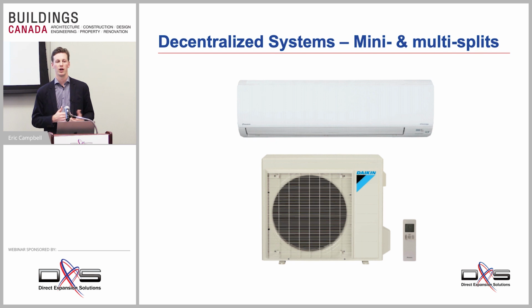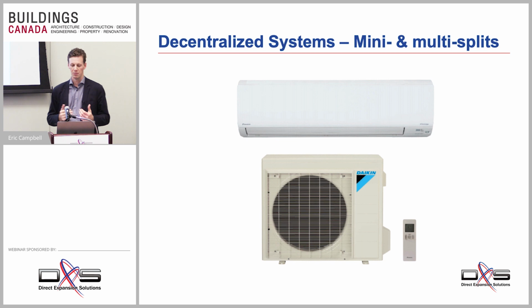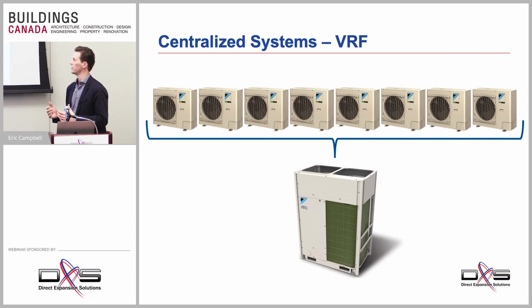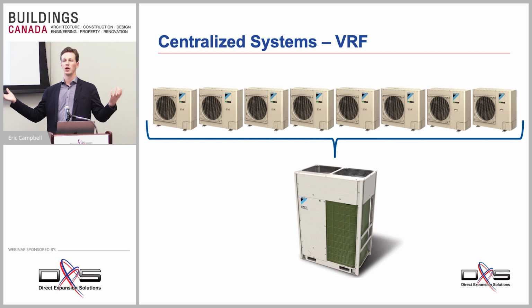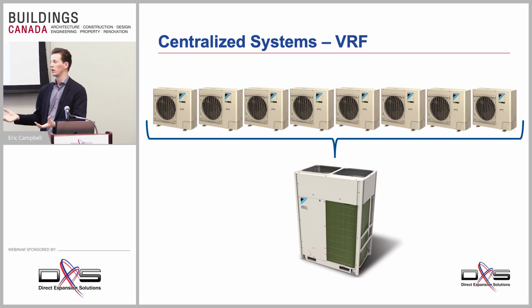These are typically one-to-one, where you've got one indoor unit and one outdoor unit. It doesn't necessarily have to be a wall-mounted ductless unit like we've shown here. There are ducted options and things like that. But simply, it is mostly a one-to-one or a two-to-one or three-to-one, where you've got maybe up to 3 indoor units connected to one outdoor unit. We'll talk later on, when we get into the design applications and considerations, about when we use this decentralized solution versus the centralized VRF solution. So VRF is like taking a whole bunch of those mini splits and combining all of those condensing units into one larger outdoor unit connected to many more indoor units, typically.